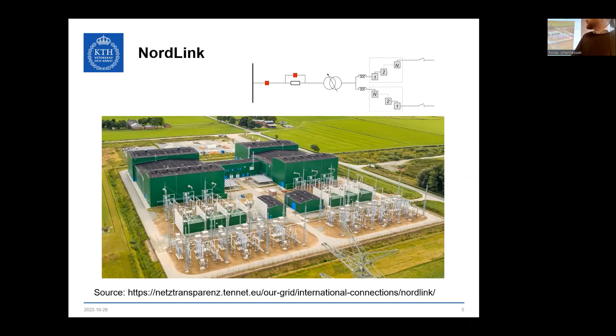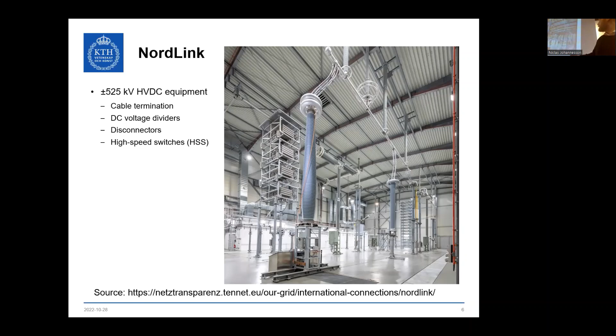So this is one picture from inside the DC hall of NordLink. Also just for scale, this is how 500 kV HVDC equipment looks like. In the front you have the cable termination, where the cable comes up from the ground, transitioning into the DC bus bar. You also have the voltage divider, which is also important later on for protections. To the left you have a big resistor, the discharge resistor. Since this is a rigid bipole, in case you get a fault in one pole, you can reconnect the cables so you get monopole operation. You also have some high-speed switches in there, some disconnectors.